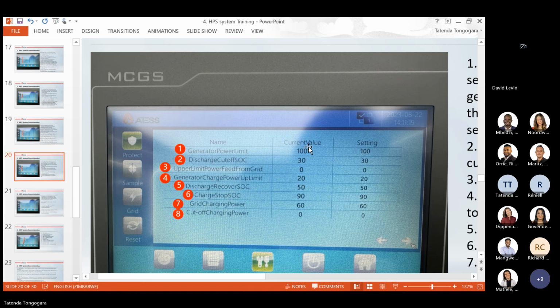So always verify these parameters, because you can run into a problem where your generator trips when it runs, because the HPS will try to take 100 kilowatt from a 100 kVA generator, of which it can only get 80 kilowatt. So always be mindful of this parameter.